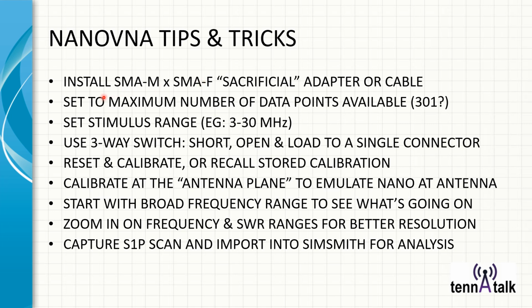Always remember to set the maximum number of data points available — it's 301 for the latest version of the firmware. I like to start with a stimulus range of 3 to 30, the full HF range, which is typical.